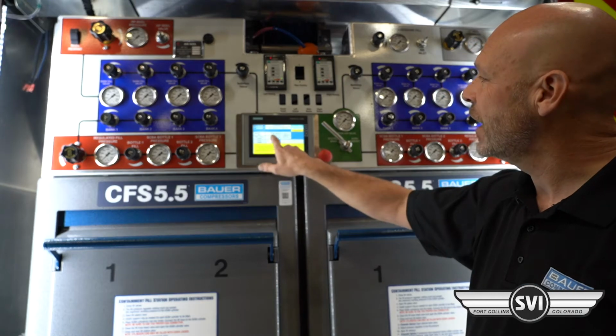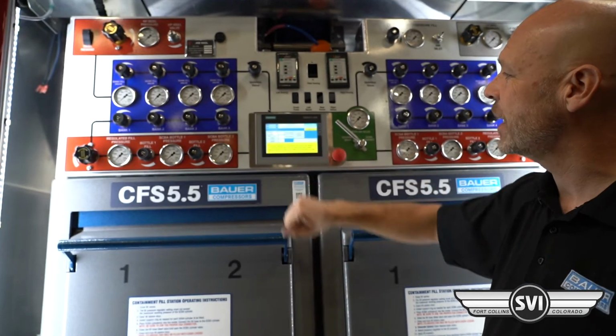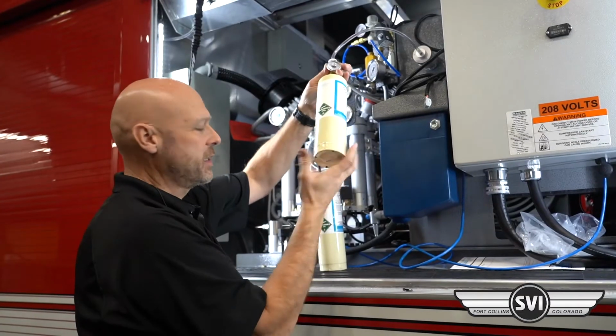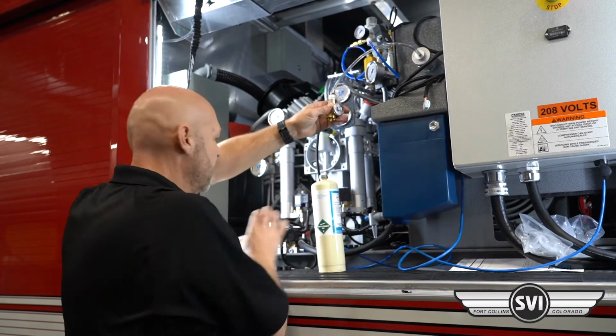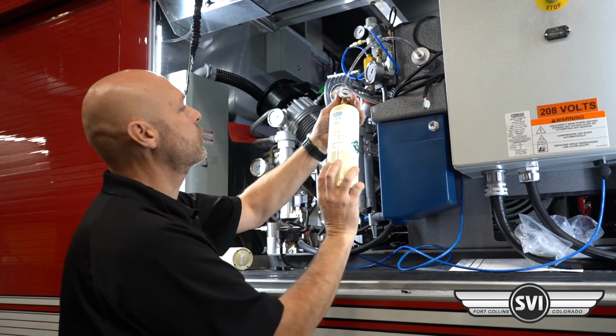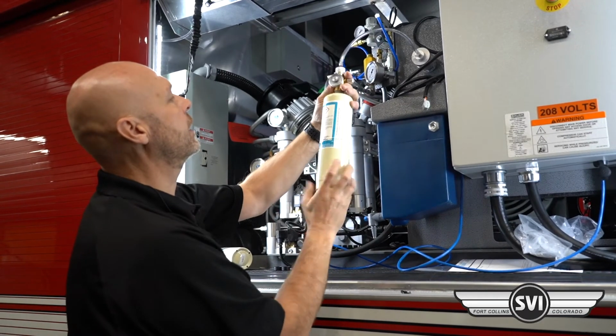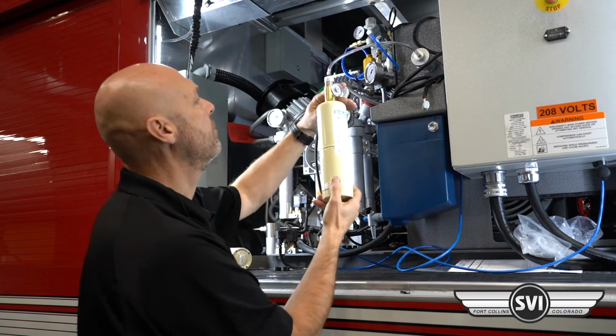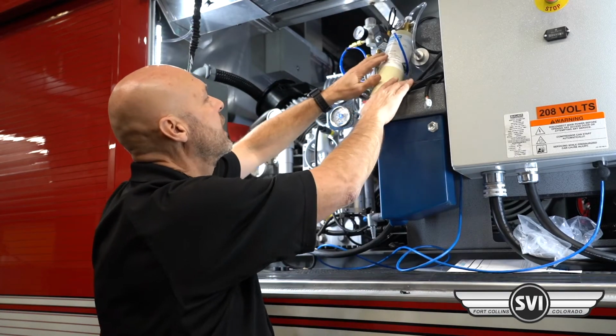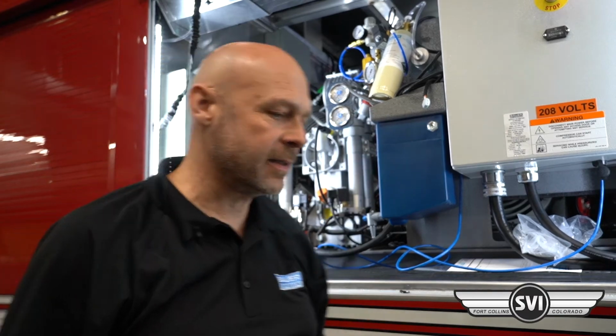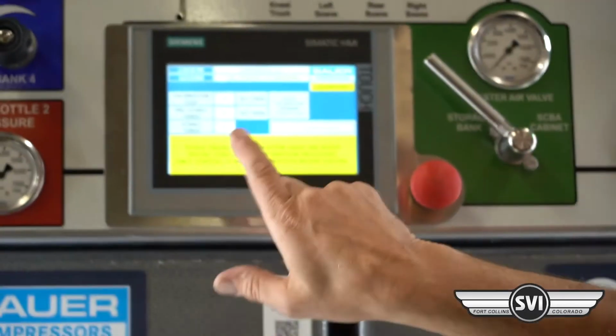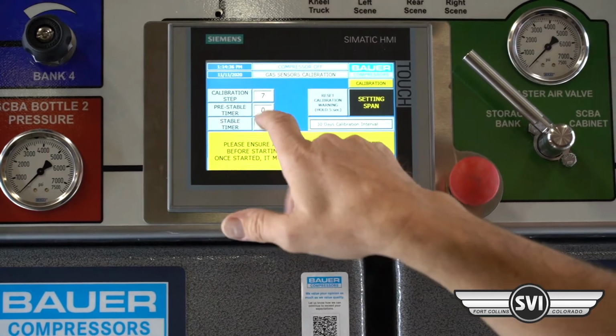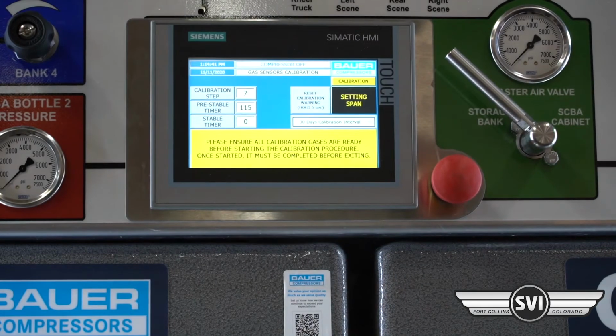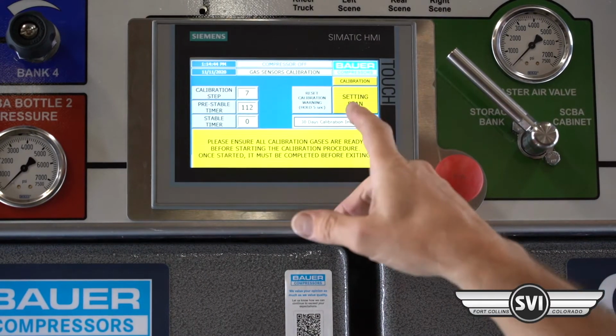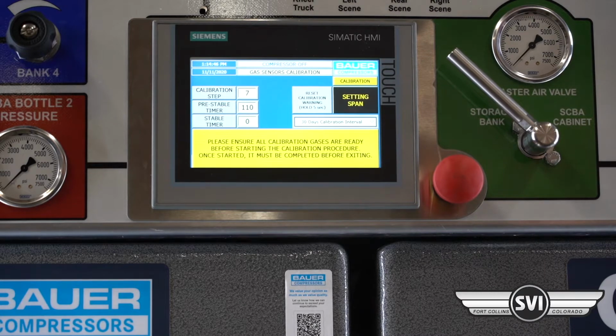So now it counted down, it went through the stable. Now we're going to set the span. So we just unscrew the 0, screw the 20 part into the regulator. Set that up there. Okay, then we'll go back. Now with the 20 part gas, we're going to set the span, and that's going to start counting down. Notice our pre-stable timer started that 2-minute countdown, so it's working. It's indicating to us that it's setting the span.